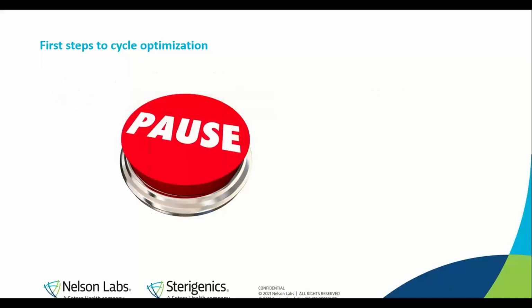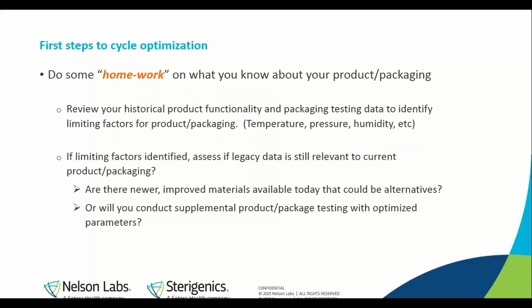Okay, this is great. But we always want to make sure that we can pause just for a minute and do some homework. If you feel that you need to adjust the temperature of your sterilization process and raise it, or you find opportunities in the pressure or humidity characteristics of your process, you want to take time and look at the historical data that you have on file. Again, we're dealing with a validated process, so you have a goldmine of information available at your fingertips, hopefully, that you can easily point to in terms of looking at what did you test for the products and for the packaging as part of your original validation.